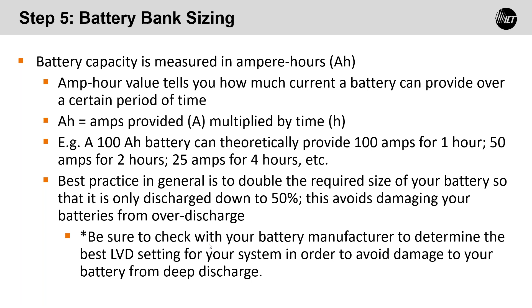So the large site example, in this case, we're going to use 1140 watts, and we're going to convert that power using this formula, I equals P over V, where I is amps, P is power, and V is voltage. So I is 1140 watts divided by 55.2. And people say, where does that come from? The upper voltage limit, the charge limit on most lead acid batteries is 13.8, I believe. And if you take that and multiply it by 4, you get 55.2. So 55.2 is going to be the upper voltage limit of a charged lead acid battery.